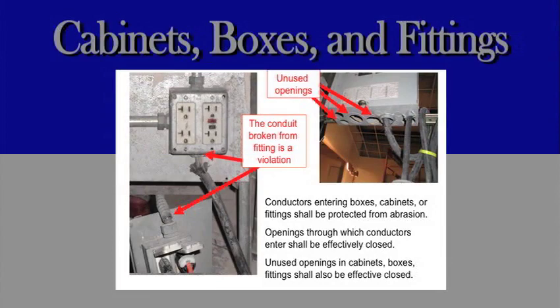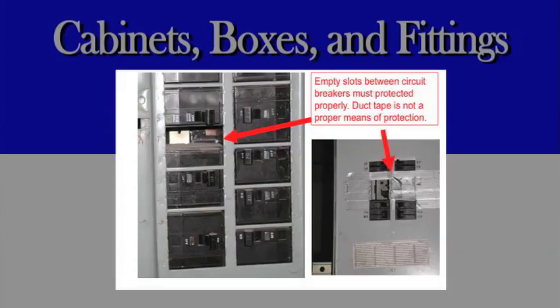Conductors entering boxes, cabinets, or fittings shall be protected from abrasion. Openings through which conductors enter shall be effectively closed. Unused openings in cabinets, boxes, and fittings shall also be effectively closed. Empty slots between circuit breakers must be protected properly. Duct tape is not a proper means of protection.